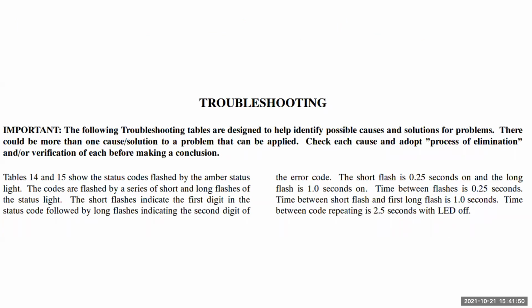Troubleshooting. We're going to go over a few flash codes here. The amber light codes will be in a series, just like on the others, where it's short and long flashes. On the status light, a short flash is 0.25 seconds, and the longer flash is 1 second. So it's just like on our regular systems. So here's several active codes: high pressure, low pressure switches, internal board failure, brownouts, compressor thermal lockout, low pressure, high pressure, condensate overflow, freeze protection.